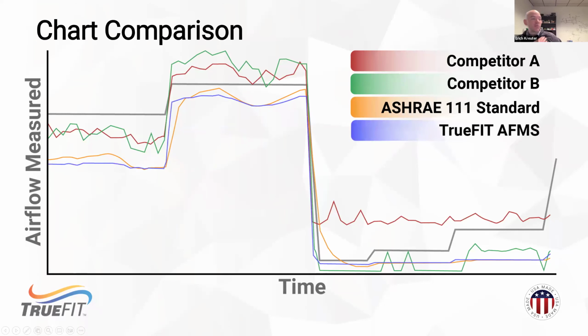The blue line here is TrueFit, and we're following that ASHRAE 111 equation spot on. Again, we're using the same measurement to profile the equipment and produce that table. So you can see that the performance really pays off. As we close that damper down, we're getting to that 111 equation very quickly, even before the thermistors acclimate. And when we get to 10 and 20% damper position, we see that those numbers are right on top of each other.